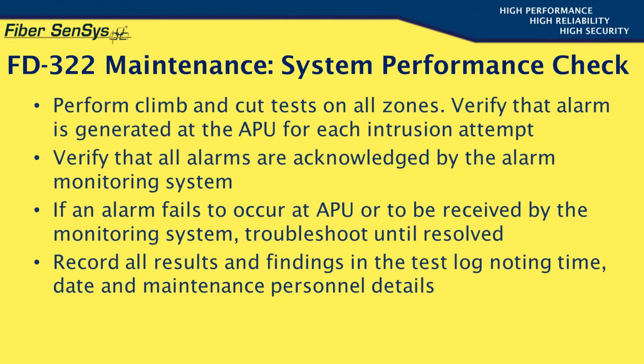It's recommended that the system performance check be done along with the visual inspection at 90-day intervals. Climb and cut tests need to be performed on every zone, making sure that each APU channel goes into alarm and that those alarms are acknowledged by the alarm monitoring system. If alarms fail to occur, or if the monitoring system does not acknowledge each alarm, troubleshoot the system to resolve the issues. Finally, don't forget to record all results and findings in the test logbook, noting time, date, and maintenance personnel details.